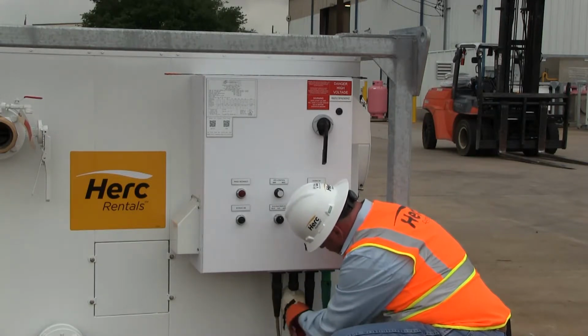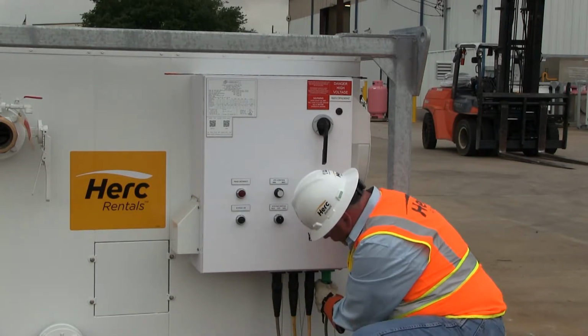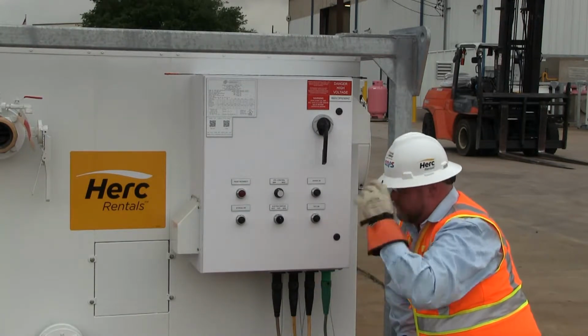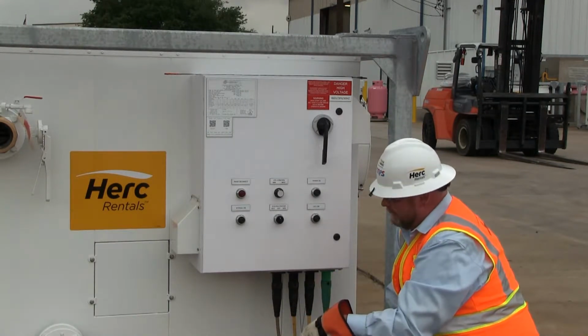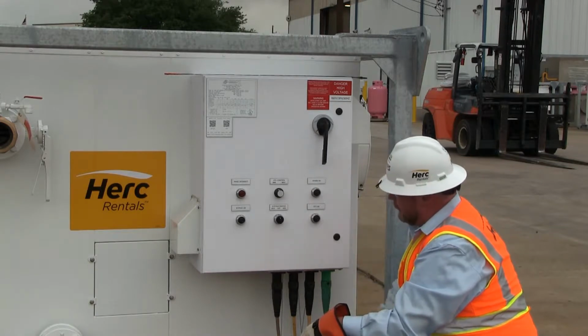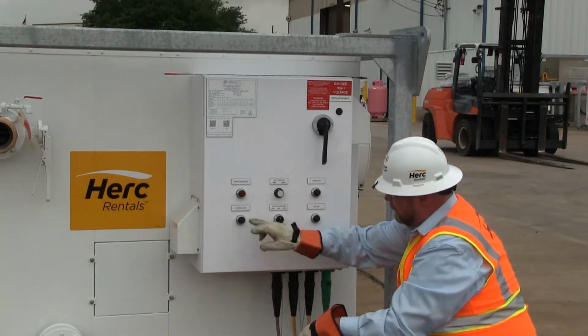Now we've got all these secured. We currently have our power source locked and tagged out. So we're going to energize our main lines here. We're going to close the circuit breaker, and we're going to verify that we have power, and we're going to verify if our phase is correct.